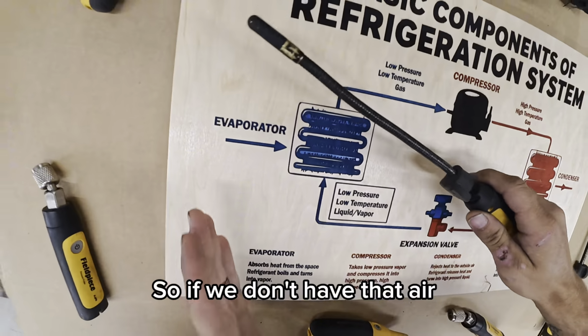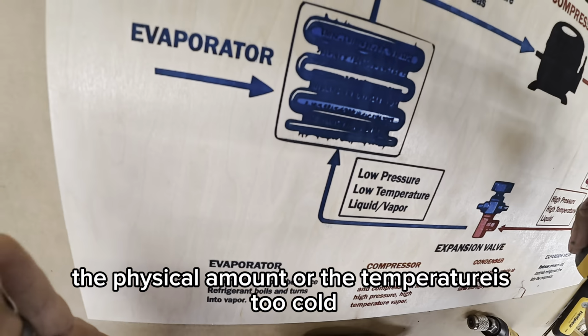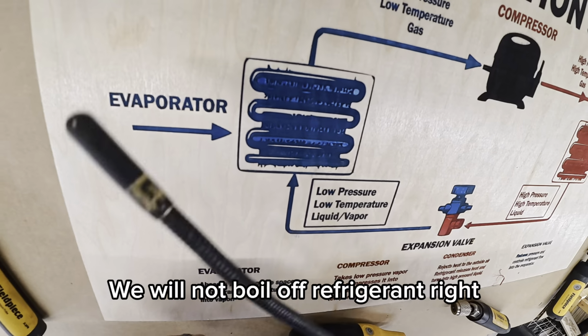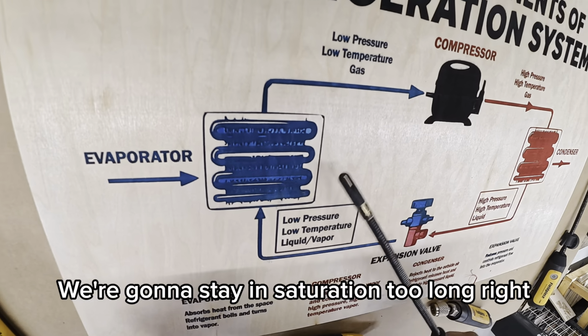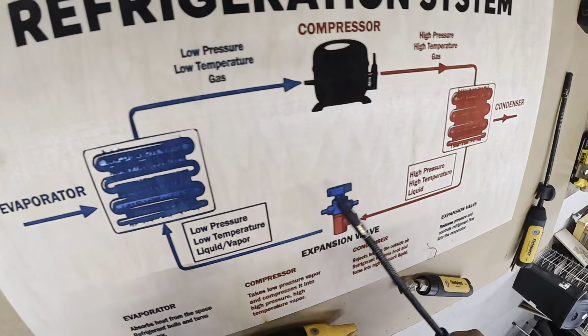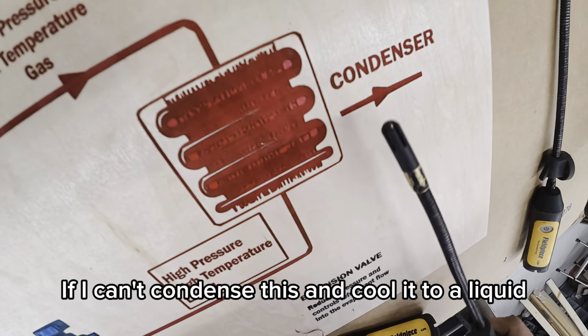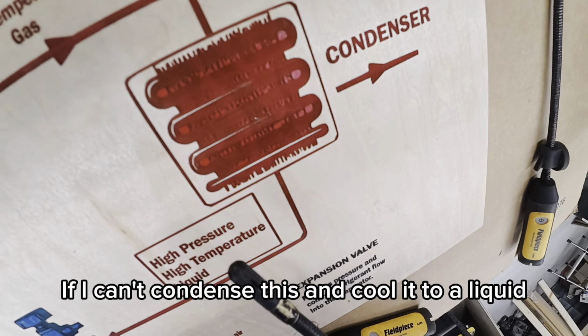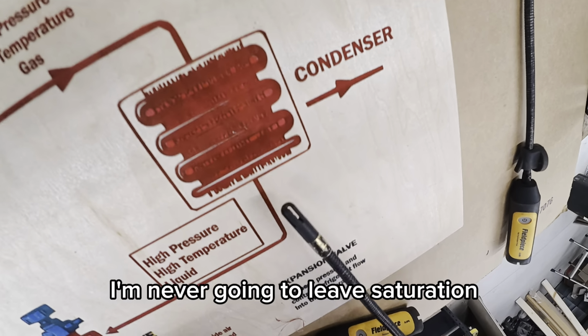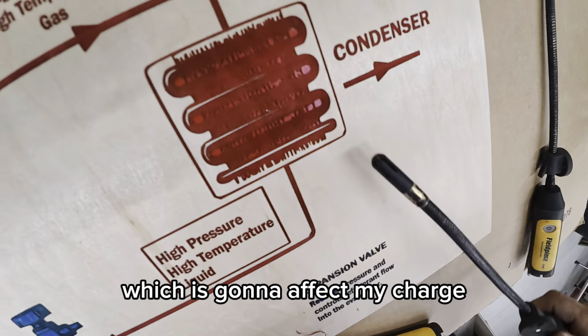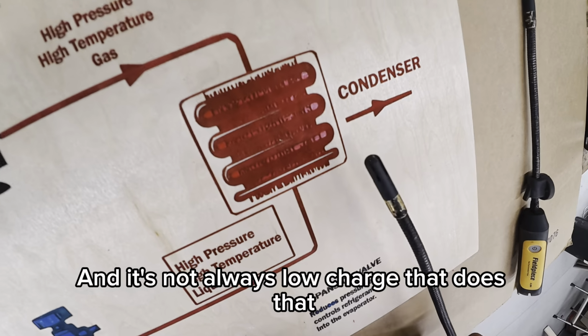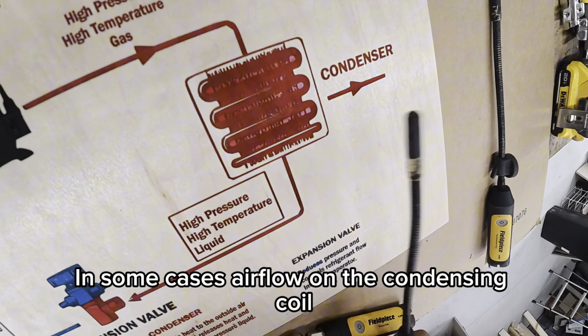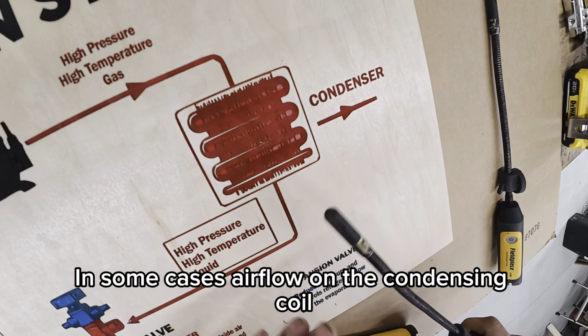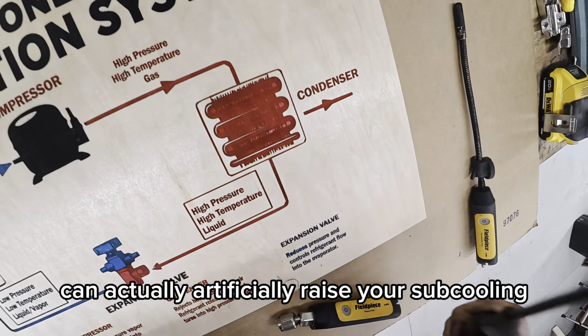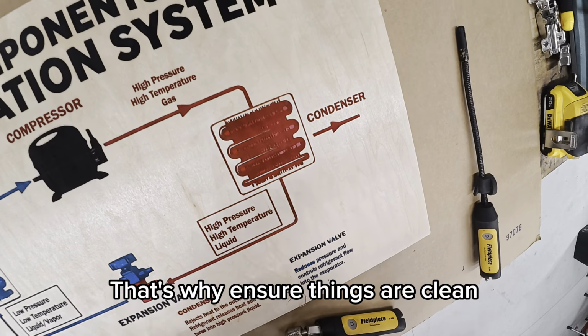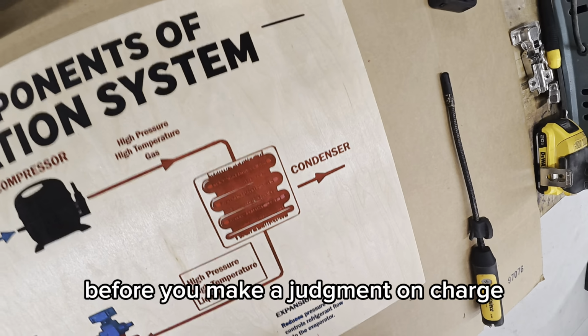So if we don't have that air, that physical amount, or the temperature is too cold, we will not boil off refrigerant, right? We're going to stay in saturation too long, right? Same thing over here. If I can't condense this and cool it to a liquid, I'm never going to leave saturation, and I'm going to have a really low subcooling number, which is going to affect my charge. And it's not always low charge that does that. It could be airflow as well. In some cases, airflow on the condensing coil can actually artificially raise your subcooling, which is crazy, but you will see that. That's why ensure things are clean before you make a judgment on charge.